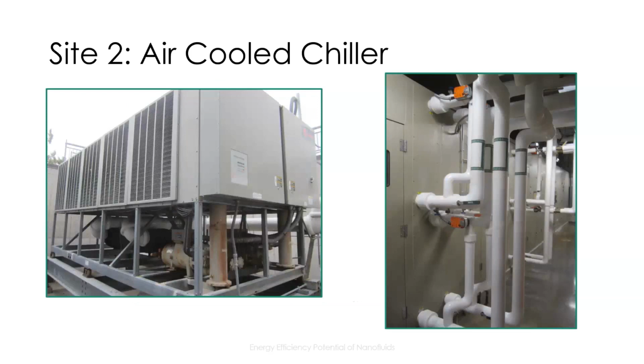The second site is the air-cooled chiller, at the same municipal office building in a different wing of the complex. This chiller served a single air handler, and our methodology for estimating the efficiency involved calculating the cooling load directly on the air handler using, again, the automation data points. We then compared this to the power input to the chiller to estimate the efficiency.